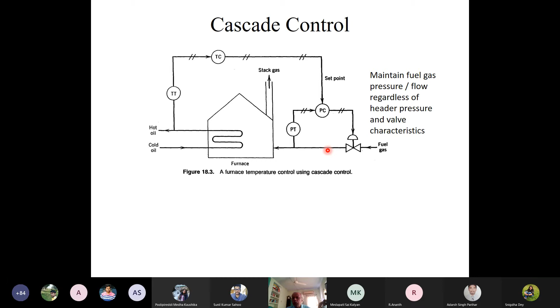So in this strategy, basically it will now maintain the fuel gas pressure or flow rate regardless of the header pressure and the valve characteristics. Here we have got two feedback controllers, TC and PC, but we have only one single control valve or single final control element. So the output signal of the master controller is the set point of the slave controller, and the two feedback controllers are basically nested as the master and slave configurations.